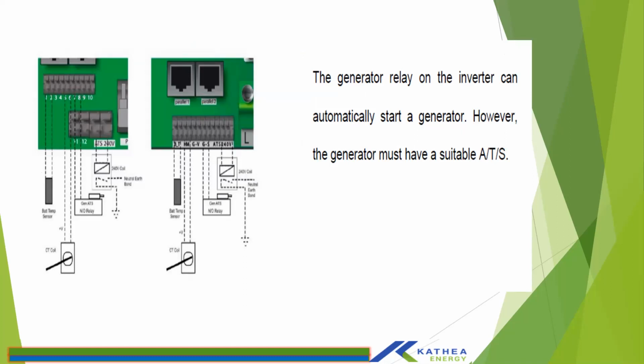There is a generator relay on the system labeled GS on the newer version of the 5 kilowatt, or 0.8 and 9, 7 and 8 on the older 5 kilowatt, and then GNS as well on the 8 kilowatt inverter. So this is the output of the ATS, which you can use to automatically start your generators. If your generator ATS uses 240 volts, then there is a 240 volt ATS function on the inverter, which you would use to start your generator. But in most cases, this 240 volt ATS function is mainly used for neutral earth bonding. That is, if your property neutral and earth are kept at different potential, you can use this ATS to energize your relay so that you'll be able to bond your earth and neutral.